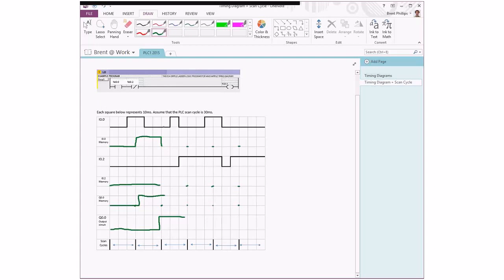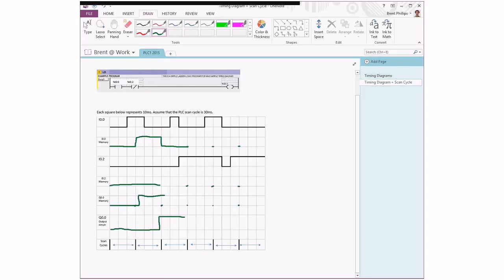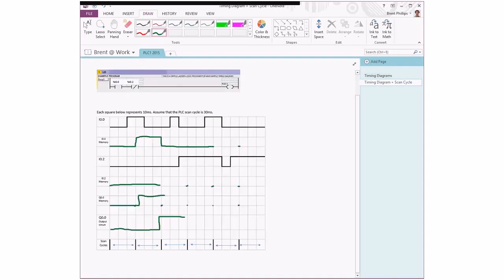So we've got here already that at the start of the scan cycle, the PLC says that the input is in an off state. So for that entire scan cycle, the memory value for that one stays off, even though there is a pulse there. That pulse actually occurred at the wrong time, so the PLC completely ignores that. At this next scan cycle we still see the same, our input stays off, until now we do get a scan cycle that corresponds with when our input is on. The value gets stored in the memory and then again the memory switches off.